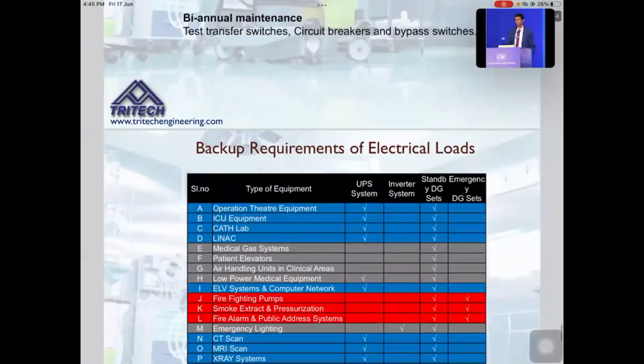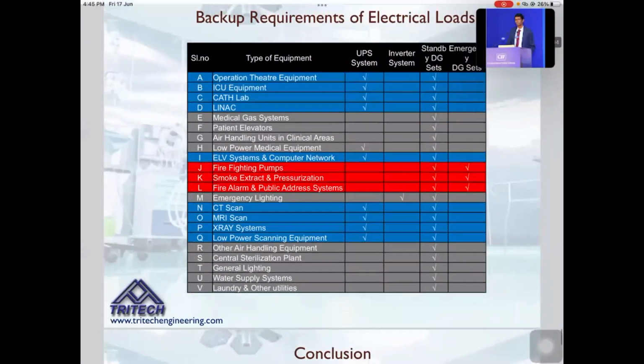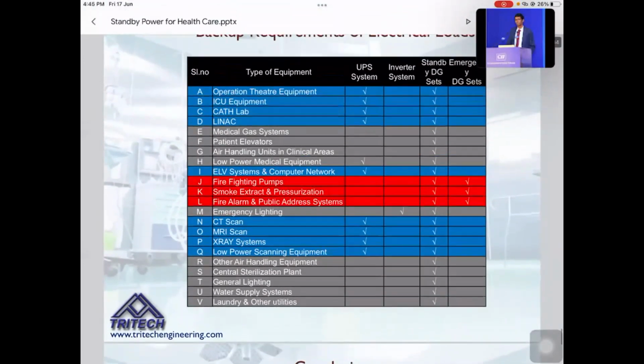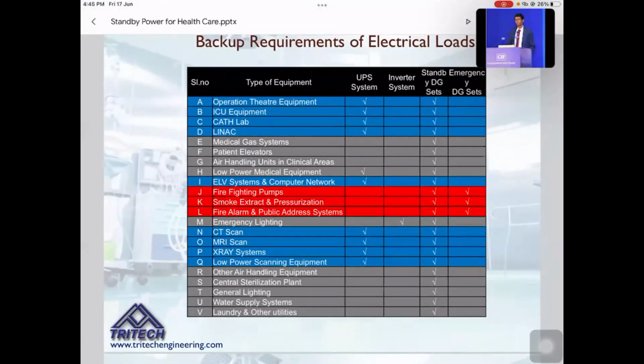I have highlighted in the last slide the standby power supply system for all different kinds of equipment: what needs to be given UPS power, what goes on inverter, what is on standby. If you look at the emergency generators, you can see that firefighting, smoke extract, and fire alarm are connected to them, which will be used only when the entire system is off in case of a fire. So this is not a backup system. You can see these 4 different categories of backup systems in operation here.